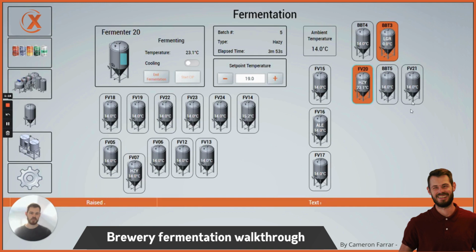We'll drop down. This is just a simulation, so the alarms aren't coming up. But if, for example, this fermenter starts to increase in temperature and the glycol valve is on and it's not cooling down, then it'll raise an alarm to the operator. And with this particular application, it can send an email, which has helped in the past. So that's the basics of the fermentation control.